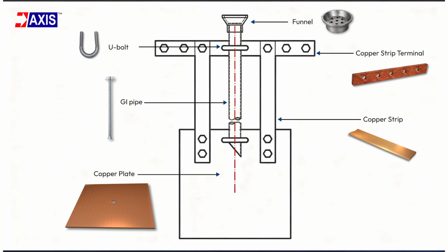Now, the U-bolt. These bolts hold the plate earthing assembly in position and keep the copper strip aligned as it rises towards the terminal. Their job is mechanical, not electrical. They make sure the strip does not bend, twist, or shift inside the pit. A stable strip helps maintain a reliable path of the fault current. I hope you now have a clear idea about the plate earthing diagram.